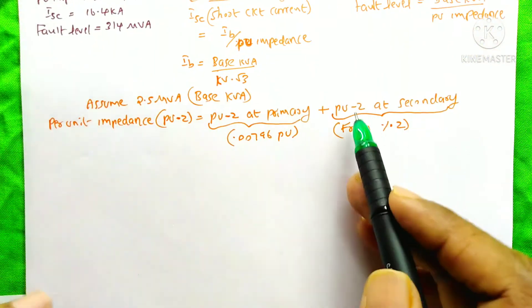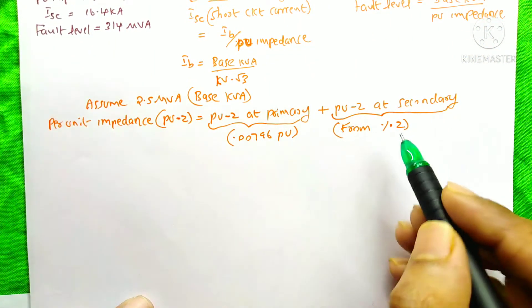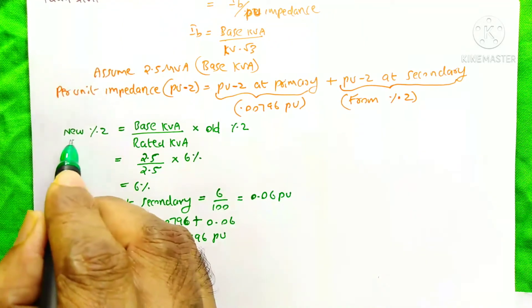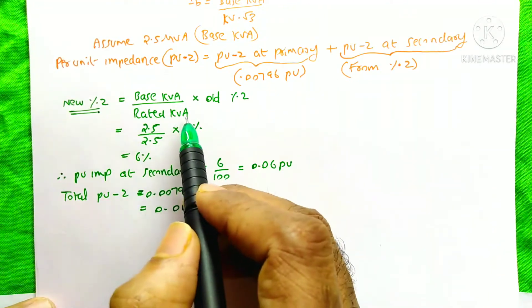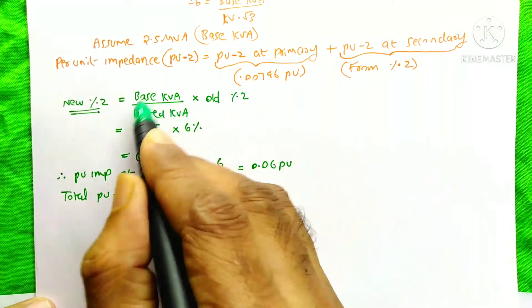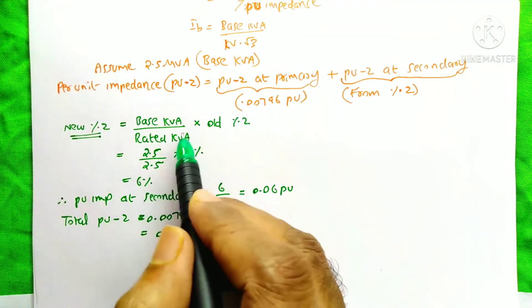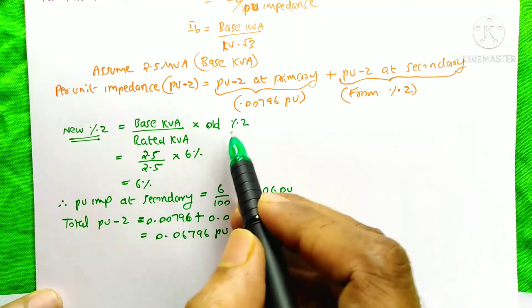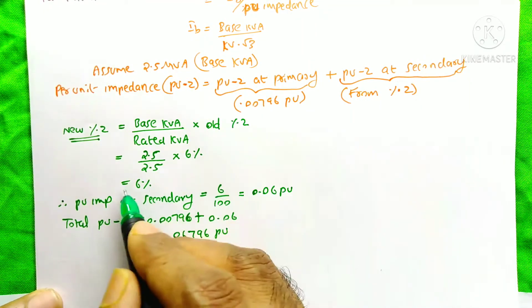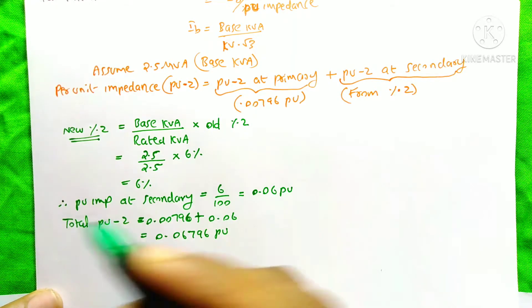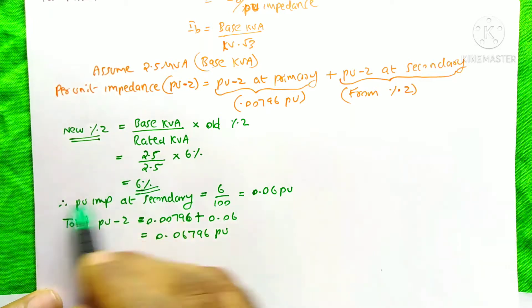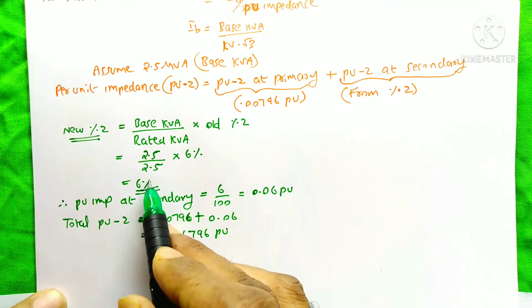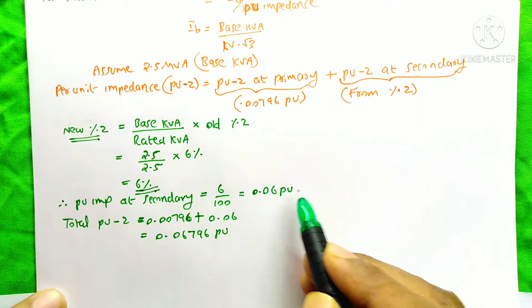The per unit impedance at the secondary side we need to calculate from the percentage impedance of the transformer, which is 6%. First, we find the new per unit impedance using the equation: base kVA divided by rated kVA, multiplied by old per unit impedance. Base kVA is 2.5 MVA, rated kVA is also 2.5 MVA, so 2.5 divided by 2.5 equals 1, multiplied by 6% gives 6%. Converting to per unit: 6% divided by 100 equals 0.06 per unit impedance.